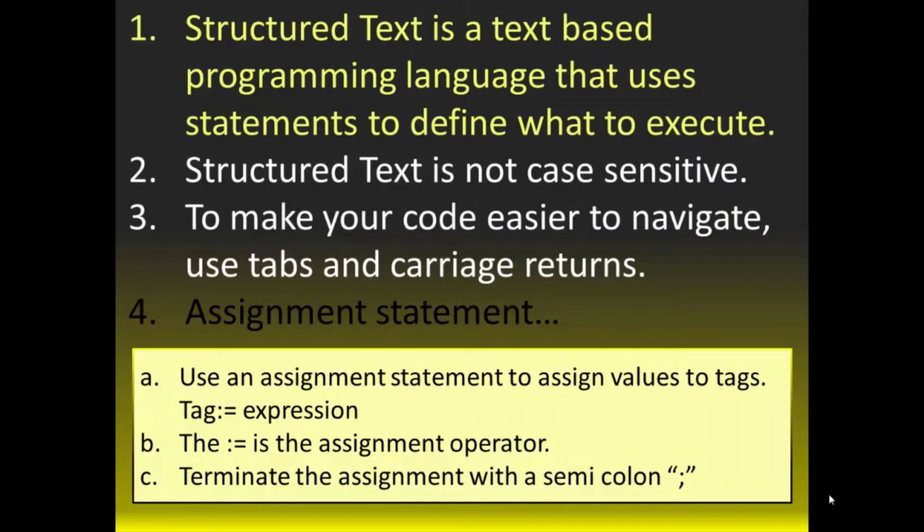I quite often will create a routine with structured text that has a fairly complex mathematical expression in it, but it references a tag from the tag database, and then it influences another tag in the tag database. That output tag, if you want to call it that, from the math expression is used in the other languages. I'm not de-emphasizing structured text. Structured text is the perfect language for certain portions of your program, but I encourage you to consider at least ladder logic diagram, function block diagrams, and structured text when you're writing your code.